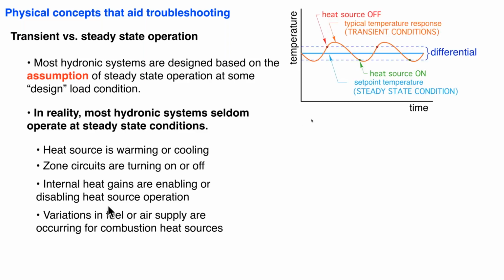And this is just an illustration. Now, when we talk about boiler outlet temperature, we'd like to think that as time goes on, some hypothetical heat source maintains some nice set point temperature. In reality, it isn't doing that. The temperature is dropping, the burner's turning on. As we inject heat into the system, the temperature is going up. We get to some upper set point condition. We shut off the burner or shut off the element, whatever's creating the heat. We coast a little higher, and then we kind of repeat that cycle. So you can see, even though we'd like to talk about, oh, the boiler's putting out 180-degree water. Well, no, it might at an instant, but in general, that temperature is varying.